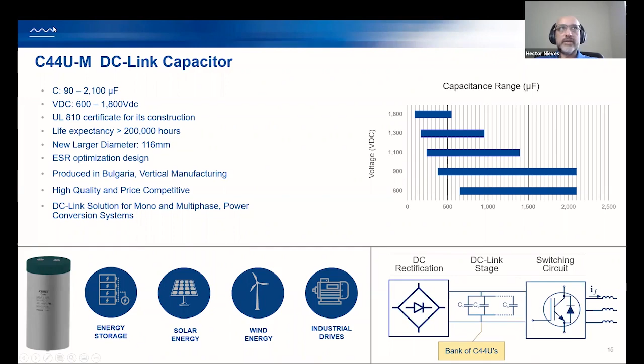And I'll talk about that in a few minutes. It has an overpressure safety device because if something happens internally to the capacitor, an overheating, this capacitor could go and disconnect by itself. And then life expectancy in this capacitor, because it's a pure AC technology, ESR is more involved, it's getting more overheating situation, and the transformation of positive and negative situation on the voltage and the current. So yes, this capacitor life expectancy is around 100,000 hours.